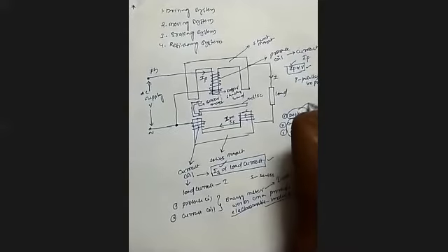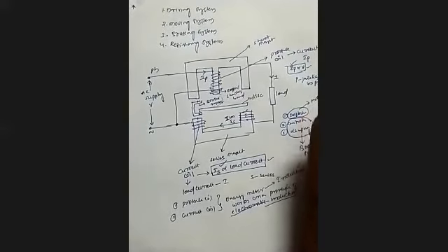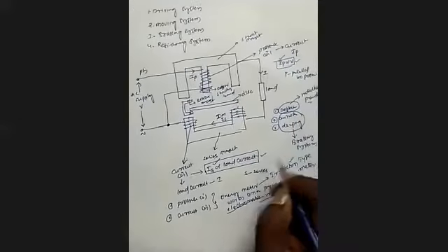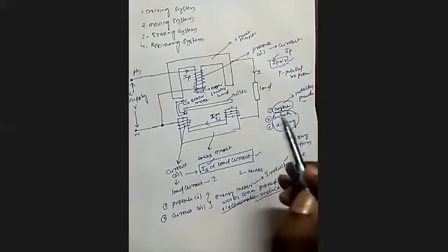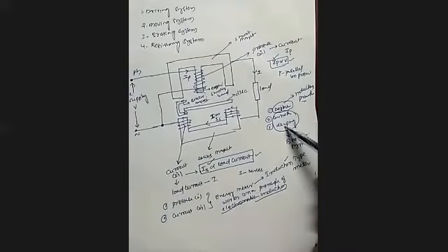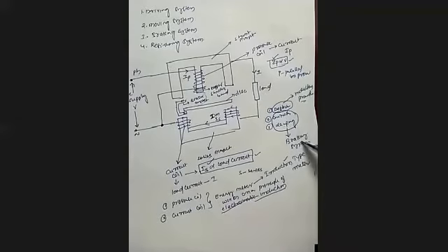The deflecting torque is produced based on the induction principle. That is the important thing. You have to understand that any measuring instrument requires deflecting, controlling, and damping torques. In an energy meter, the deflecting torque is provided by the induction principle. The controlling and damping are both provided by the braking system.